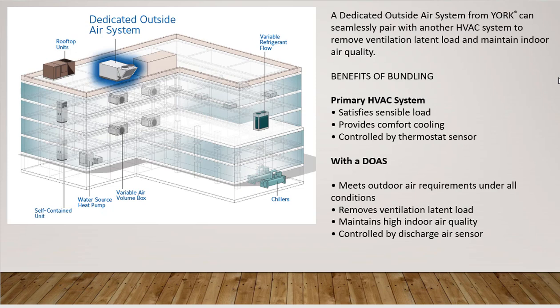So we are getting these benefits from the primary HVAC system, such as VRF terminals or other terminal units. We are getting satisfied sensible load, comfort cooling, and control by thermostat sensor. With the DOAS, we can meet the outdoor air requirement under all conditions, remove ventilation latent load, and maintain high indoor air quality, and it can be controlled by a discharge air sensor.